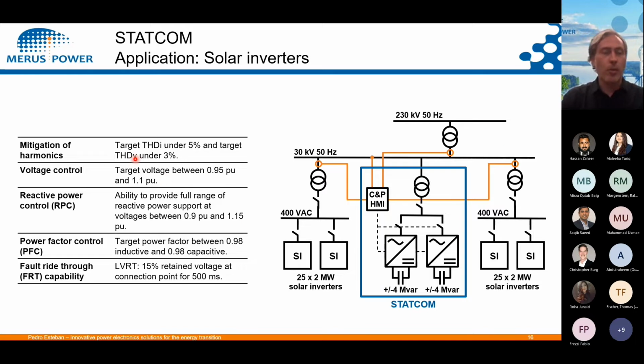Here are some examples of typical values that customers are requiring. Very typical for harmonic mitigation is having a very low total harmonic distortion in current and voltage, a certain voltage control, minus 5 to plus 10%, and the ability to control reactive power or give reactive power support when needed for the installations. Power factor is also important. It has to be close to 1, of course; closer is always better. And some fault ride-through capability is also a common requirement.